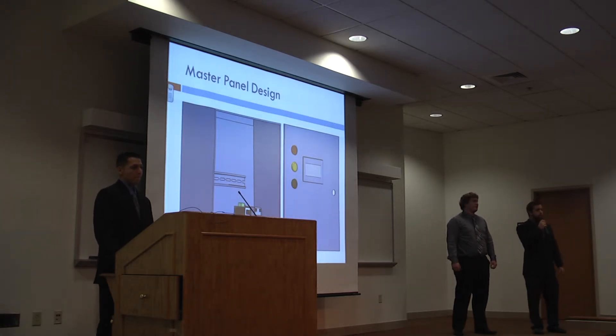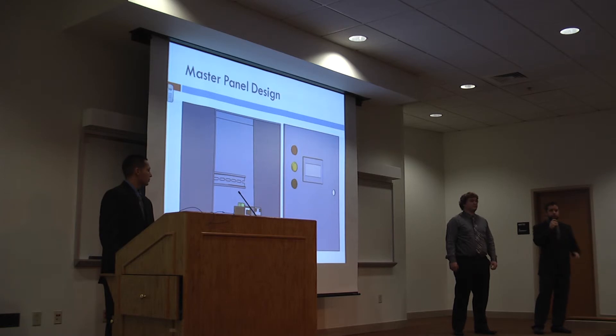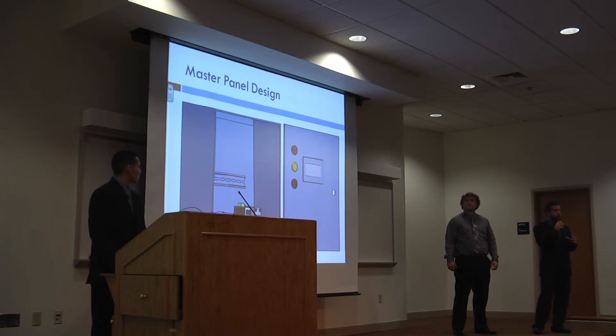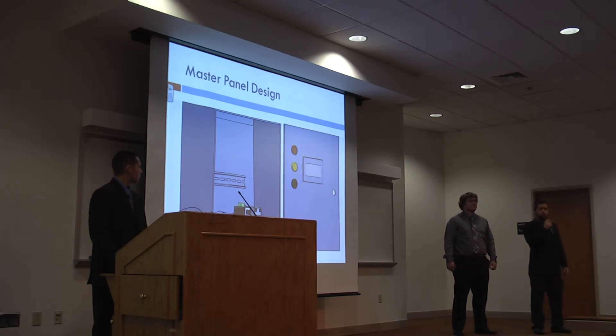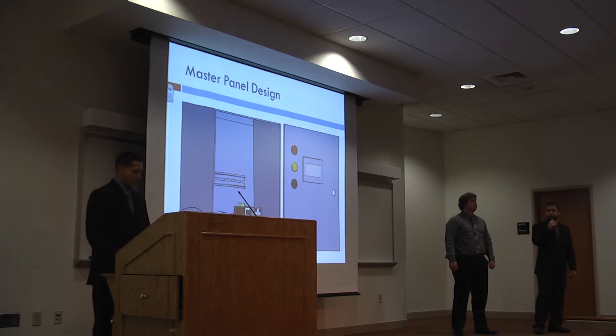This shows the master panel design. For the internals, from left to right, you can see the terminal blocks, the ethernet switch which connects all of the master panels and satellite panels, and then the power supply. On the front door, the square is the human-machine interface — basically the brains of the operation — and then your red button for your emergency, your yellow button for your help, and your black button for your master reset.